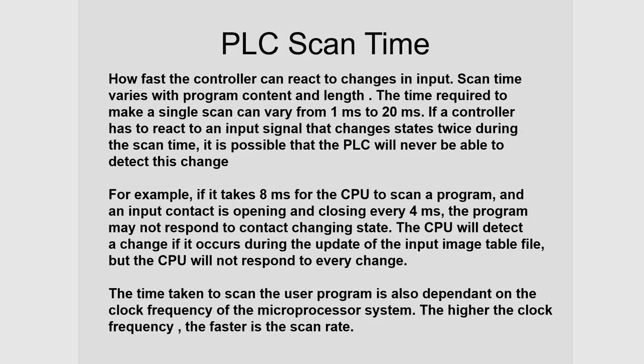It doesn't happen instantaneously. And the more complicated the device, that is, if you're using a timer or counter instead of a regular coil or contact, and the more logic you have on the rung, the longer this process is going to take.